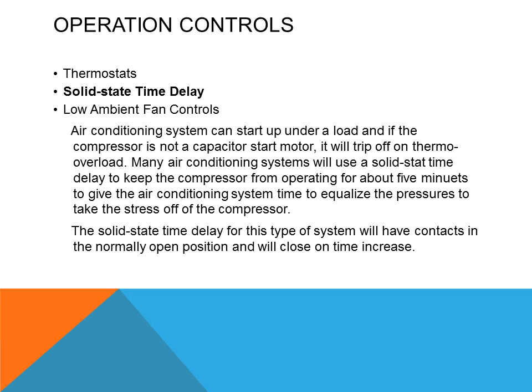Air conditioning systems can start up under a load, and if the compressor is not a capacitor-start type of motor, it will trip off on thermal overload. Many air conditioning systems will have a solid state time delay to keep the compressor from operating for about five minutes, to give the system time to equalize the pressure and take the stress off the compressor. The solid state time delay contacts are in the normally open position and will close on time increase.